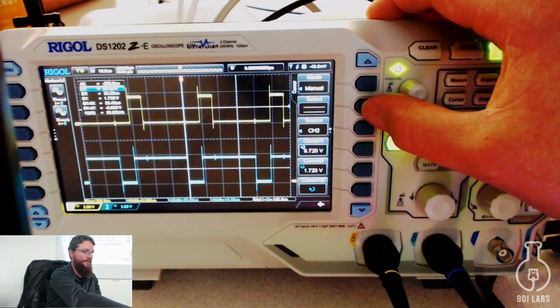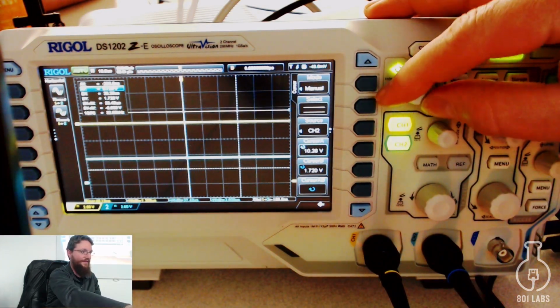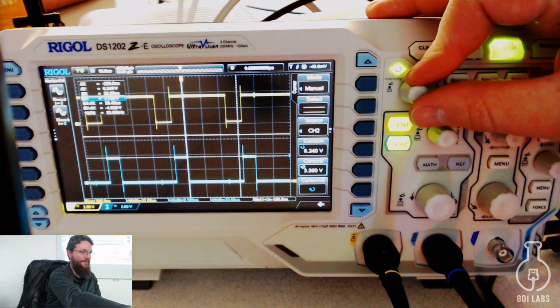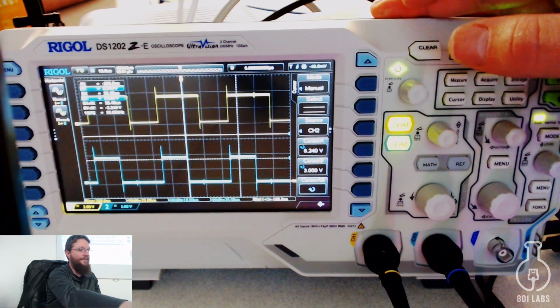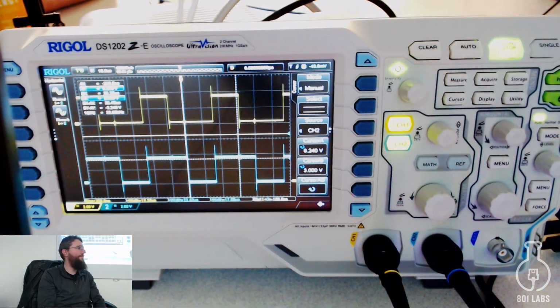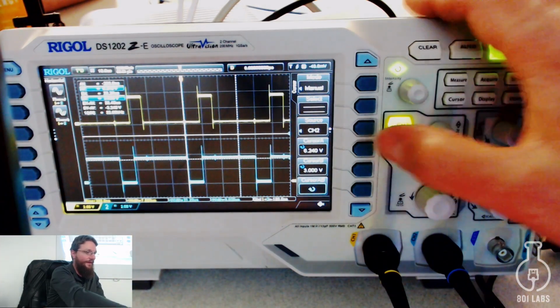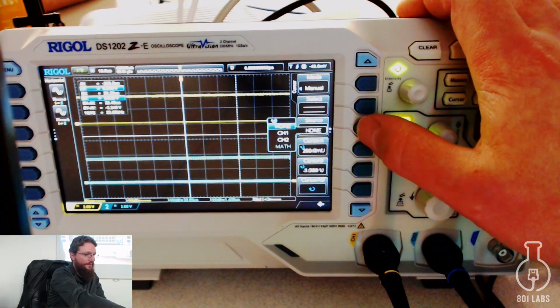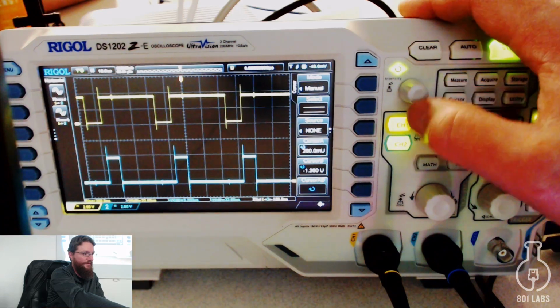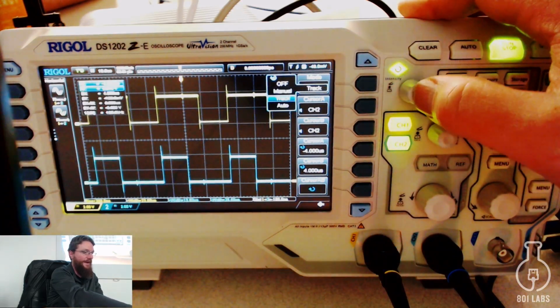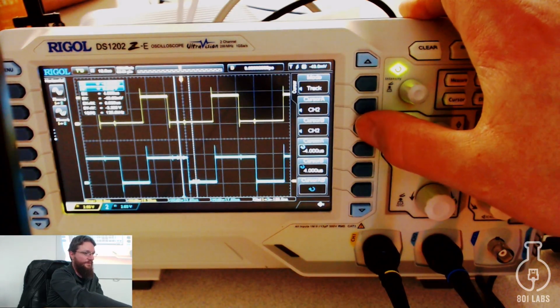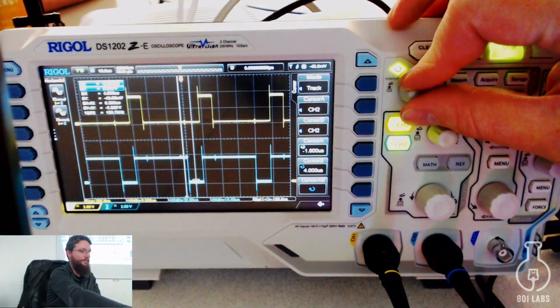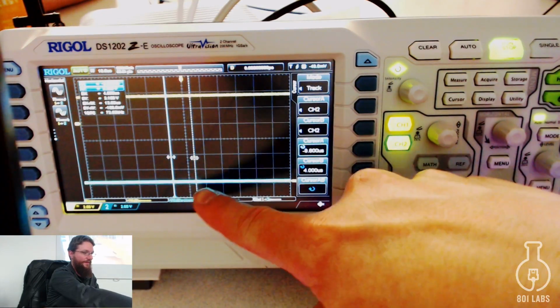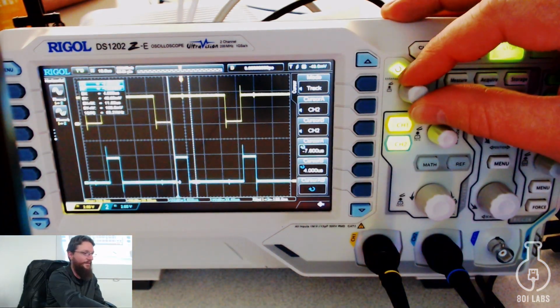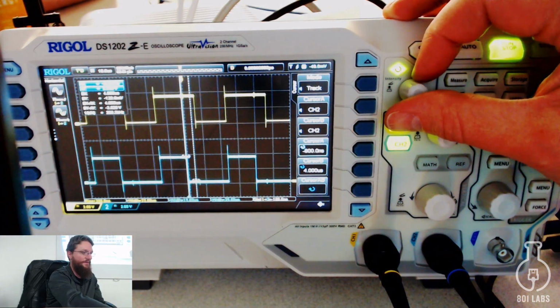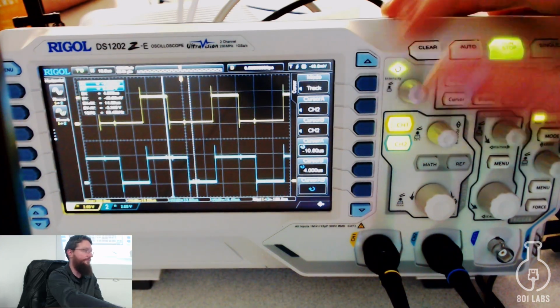If you want to use vertical cursors instead of horizontal, you hit this select button, and then you can move cursor 1 and cursor 2, again by pressing the intensity button. The intensity button kind of doubles as your selector knob whenever it's not being used for intensity. And then the source on this doesn't particularly matter for manual cursor measurement, but if you're using other cursor modes like track, it will attempt to align with parts of the signal when you turn the knob. So you can see like these little white blurry things that are probably really hard to see on the camera are jumping up and down with the signal, and they'll snap to corners, edges, whatever they can find, basically.